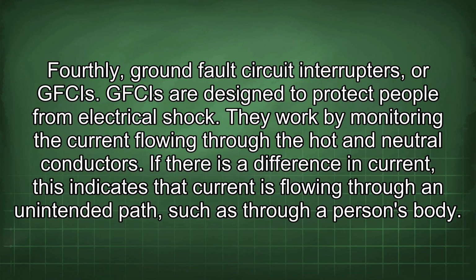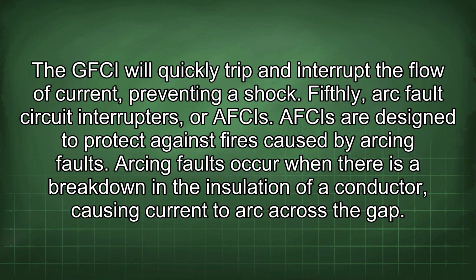Fourthly, ground fault circuit interrupters, or GFCIs. GFCIs are designed to protect people from electrical shock. They work by monitoring the current flowing through the hot and neutral conductors. If there is a difference in current, this indicates that current is flowing through an unintended path, such as through a person's body. The GFCI will quickly trip and interrupt the flow of current, preventing a shock.